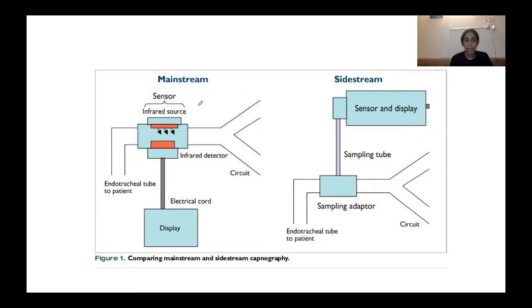So this is your mainstream and side stream. Endotracheal tube to patient. This is the sampling adapter. This is the sampling tube. A sample will be taken from here to the sensor and the display unit, which is located away. Because of this tube, there can be kinking, cutting, or clogging of the tube, and also there can be a delay. However, it is lightweight, there is no traction, and it can be used in prone positions.